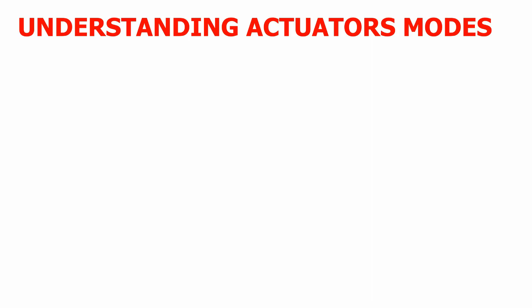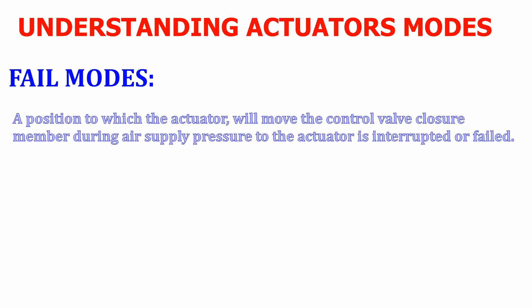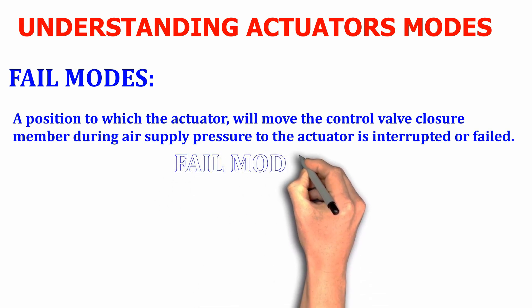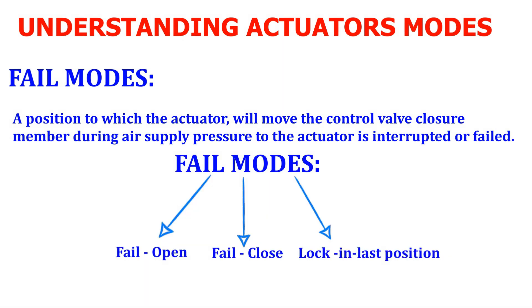So what is basically a failsafe mode? It is the position to which the actuator will move the control valve closure member — that is the plug — if the supply air pressure fails or gets interrupted. We have different types of failsafe modes: failsafe open, failsafe close, and lock-in last position.